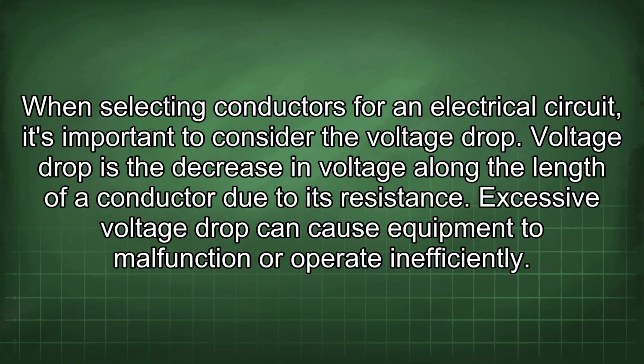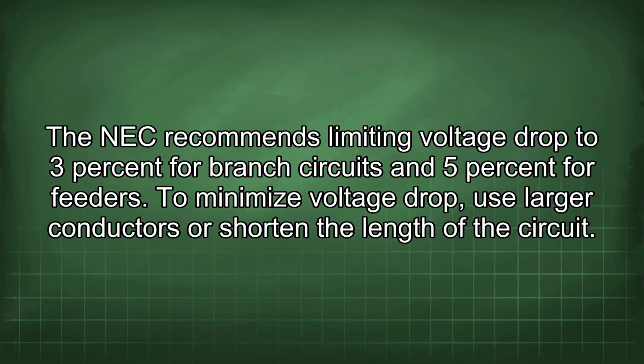When selecting conductors for an electrical circuit, it's important to consider the voltage drop. Voltage drop is the decrease in voltage along the length of a conductor due to its resistance. Excessive voltage drop can cause equipment to malfunction or operate inefficiently. The NEC recommends limiting voltage drop to 3% for branch circuits and 5% for feeders. To minimize voltage drop, use larger conductors or shorten the length of the circuit.